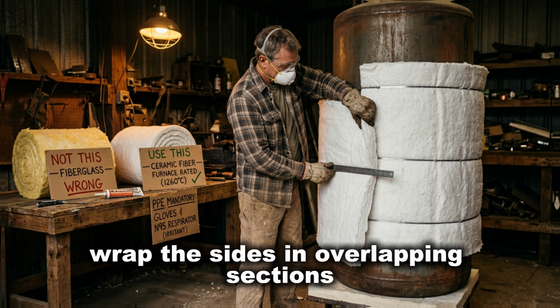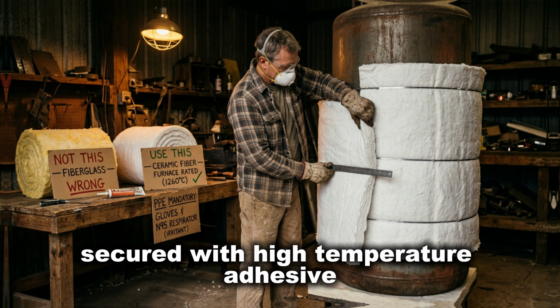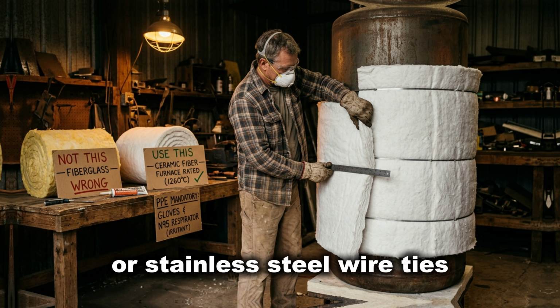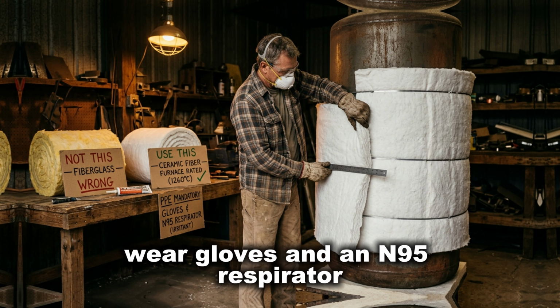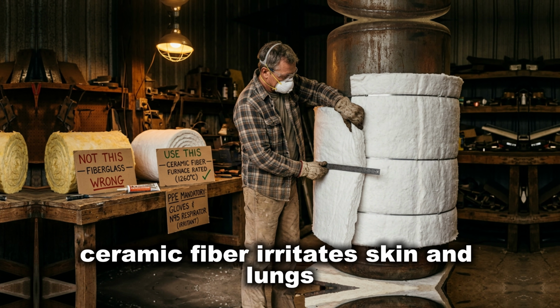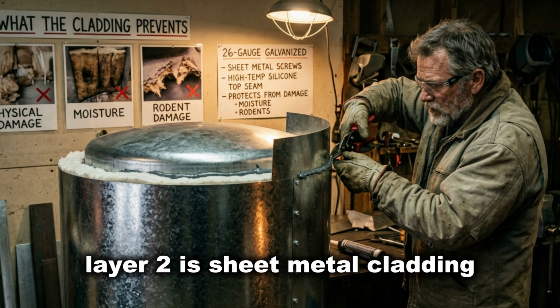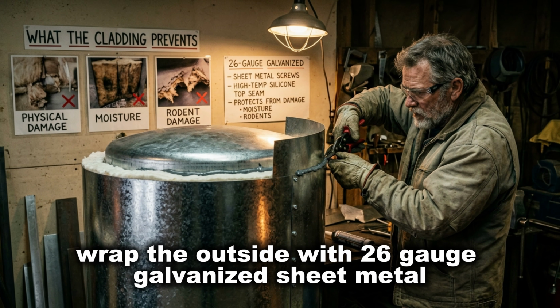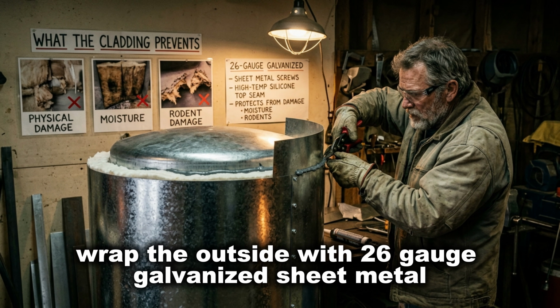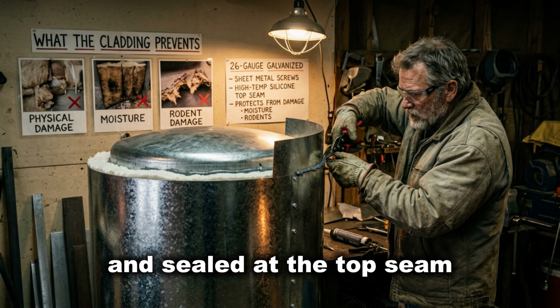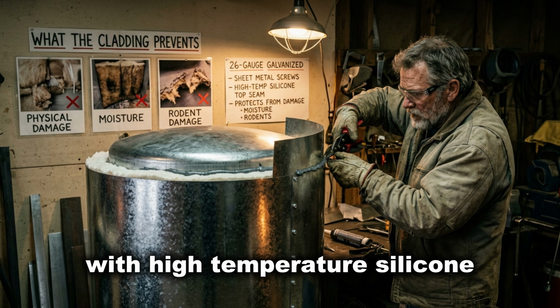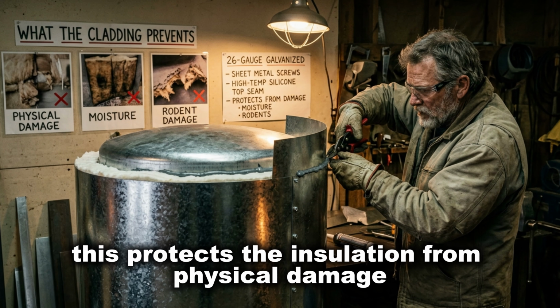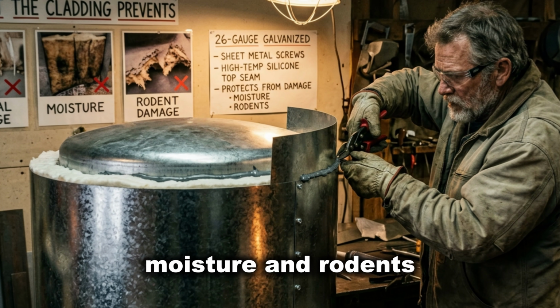Wrap the sides in overlapping sections secured with high-temperature adhesive or stainless steel wire ties. Wear gloves and an N95 respirator. Ceramic fiber irritates skin and lungs. Layer 2 is sheet metal cladding. Wrap the outside with 26-gauge galvanized sheet metal, fastened with sheet metal screws, and sealed at the top seam with high-temperature silicone. This protects the insulation from physical damage, moisture, and rodents.